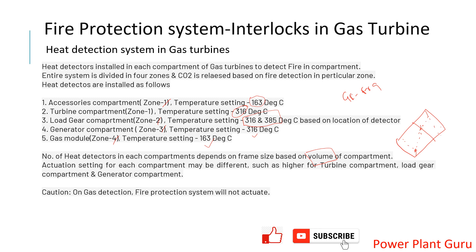An important point to note is that there are also separate gas detection systems, and we should not confuse them with the fire protection system. This is a hazardous gas detection system that may be triggered due to a fuel leak or any hydrocarbon leak. The CO2 suppression system will not actuate based on this hazardous gas detection — it is a separate system.